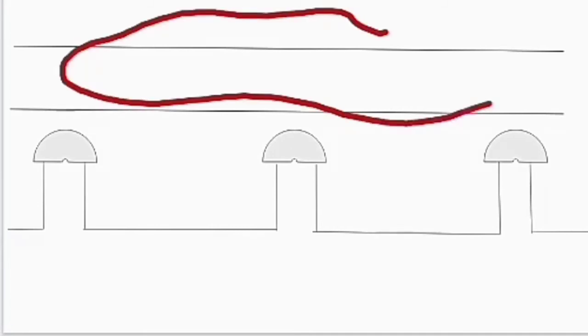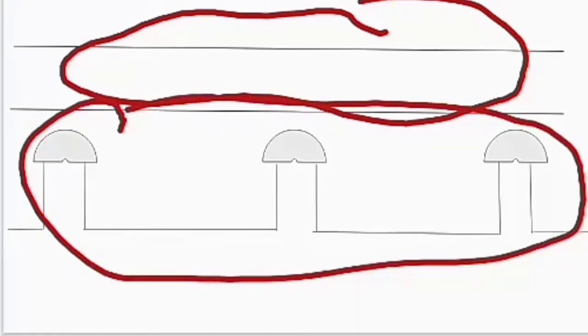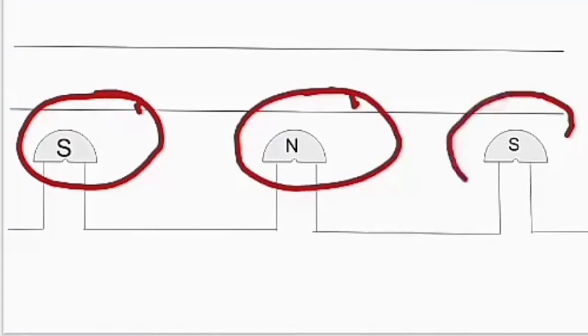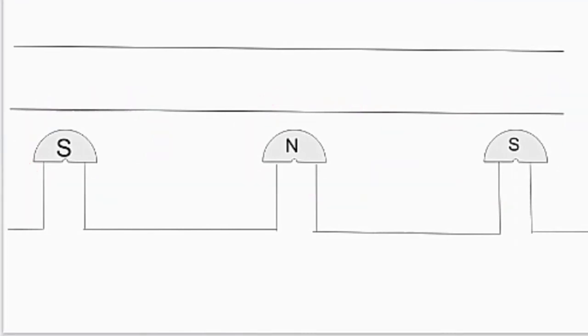Now explaining the concept through flux lines. Here is the stator without conductors and the rotor part. We give supply to the rotor, and poles appear — south pole, north pole — alternating. We then rotate the rotor in the clockwise direction. After that, we place conductors following a lagging power factor load, because under short circuit the stator winding behaves like a purely inductive load.